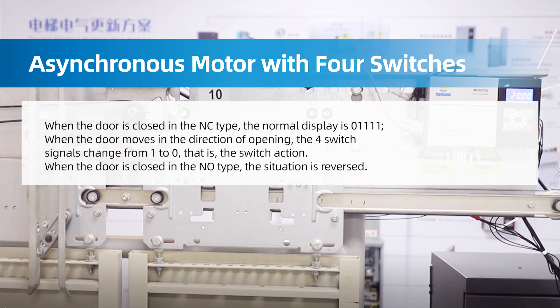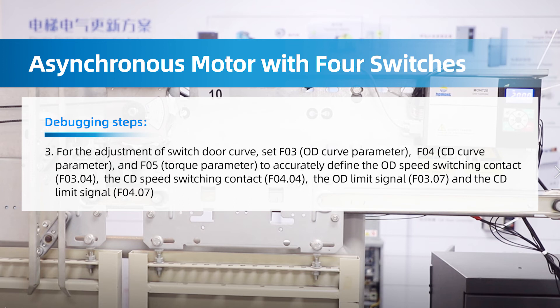When the door is closed in NO type, the situation is reversed. For adjustment of the switch door curve, set F03 (OD curve parameter), F04 (CD curve parameter), and F05 (torque parameter) to accurately define the OD speed switching contact F03.04, the CD speed switching contact F04.04, the OD limit signal F03.07, and the CD limit signal F04.07.